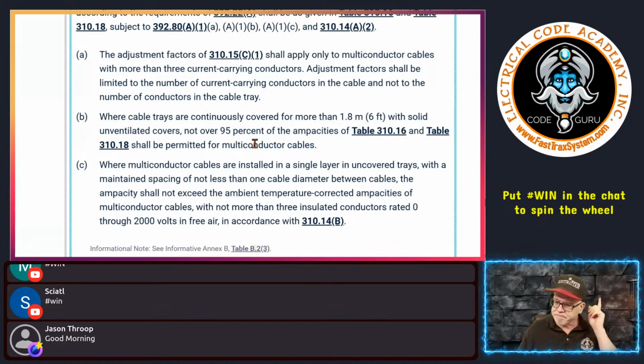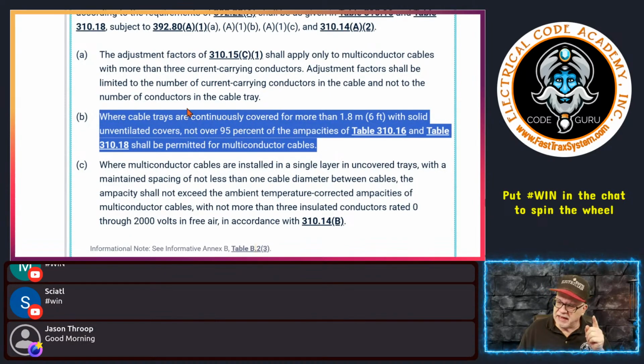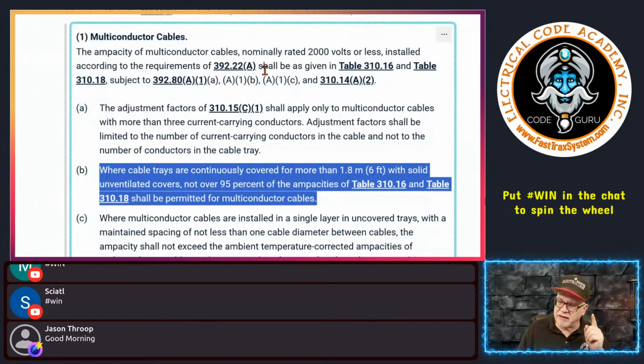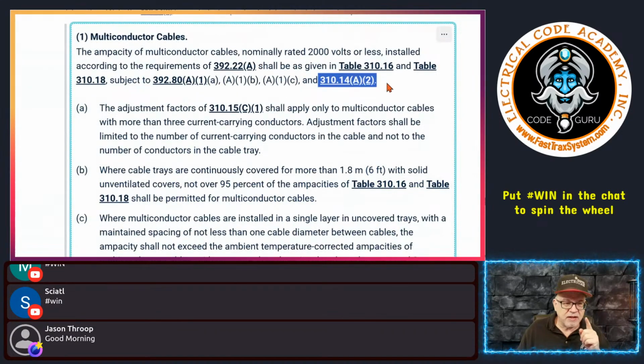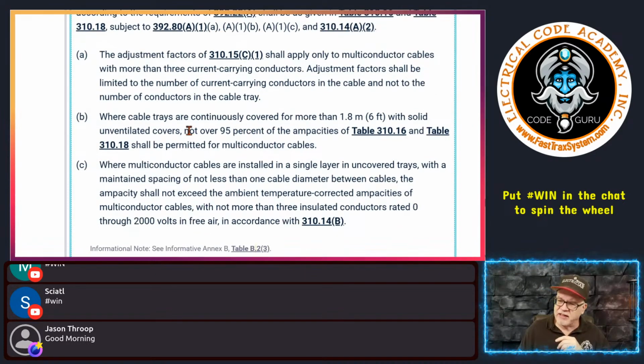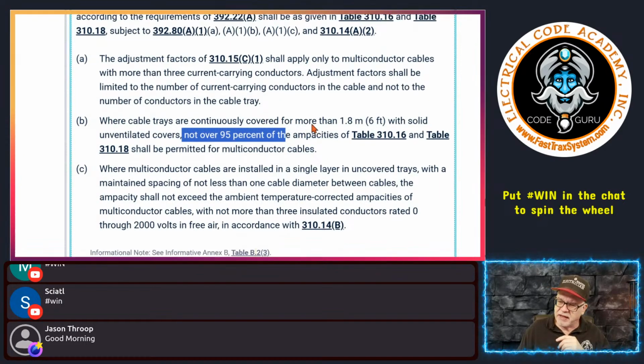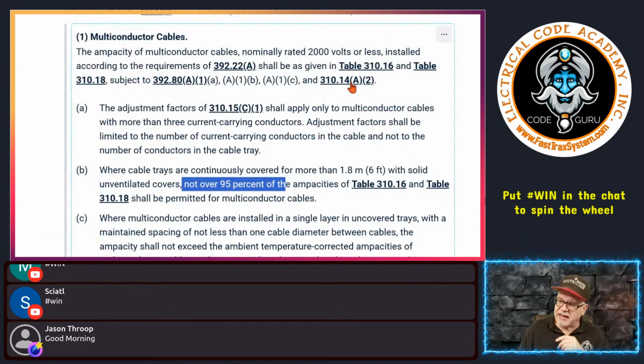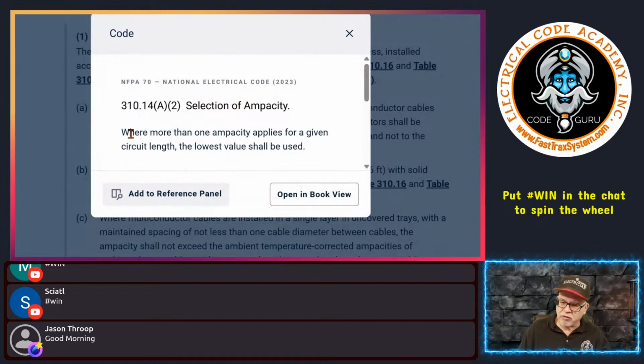Okay, now there's something I need to point out here. Even with this in play, don't forget the charging statement said this. This is really important for the engineers who are designing it and inspectors who look at this and say, wait a minute, you can't exceed 95% of the ampacity right here, right? But if this rule is in play, and I'll show you this rule, here's where it says where more than one ampacity applies to a given circuit length, the lowest value shall be used.